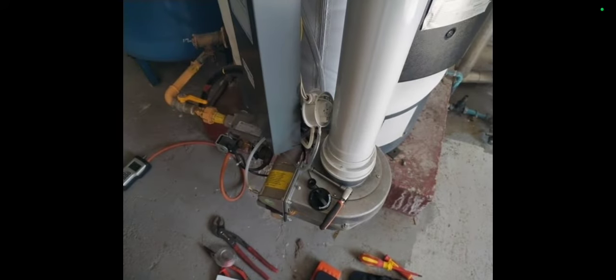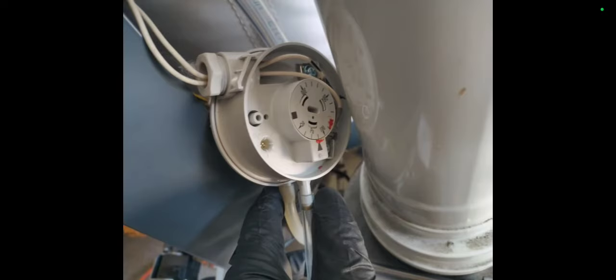I'll tell you what was happening. Basically, the fan was running when I came to it. The power was off, I turned the power on to it. Then the fan was running, but the boiler wasn't going to ignite. So straight away, I thought to myself, it's the air pressure switch sensing that the fan's running. The fan sounds okay. Is the fan running strong enough? So I looked at the flue, had a little wiggle of the flue. So I had a look at the air pressure switch, and it looked like it wanted just over 100 pascals in order to activate.